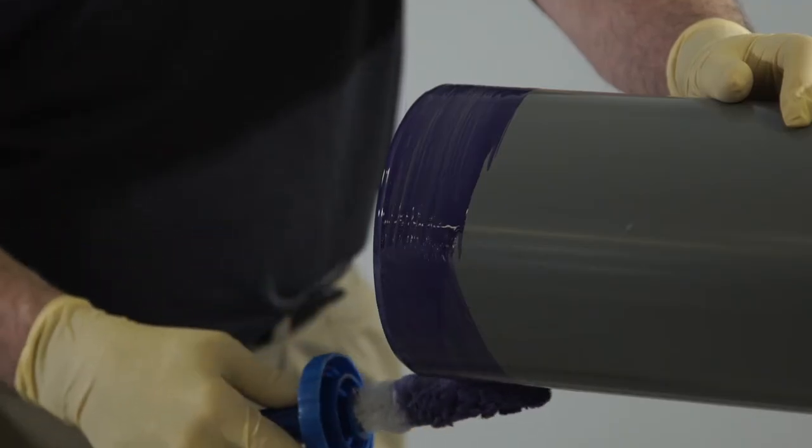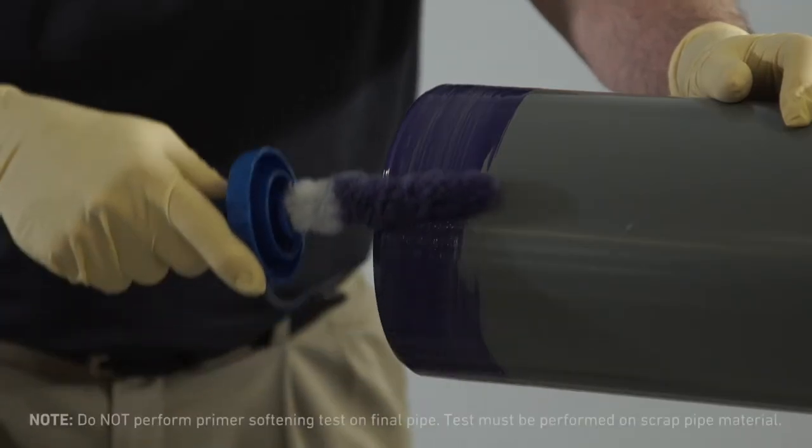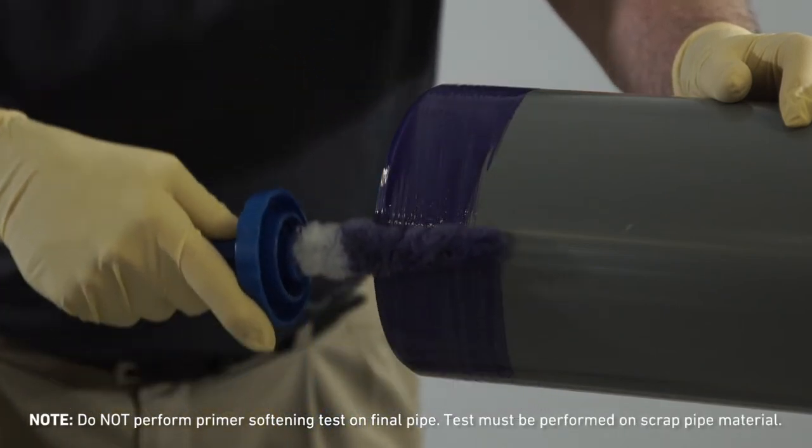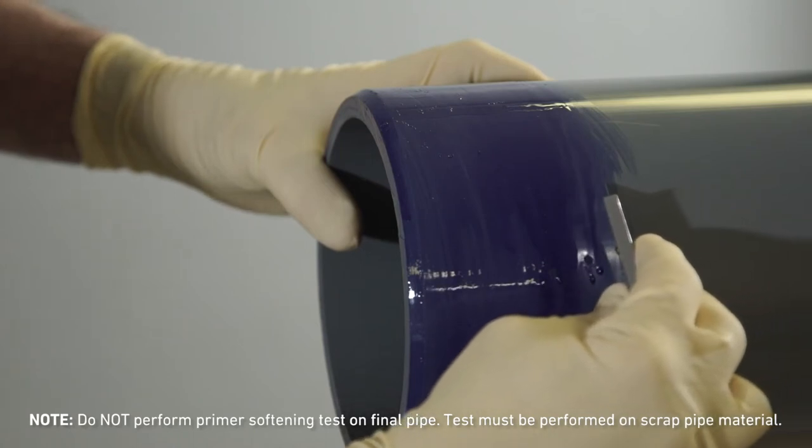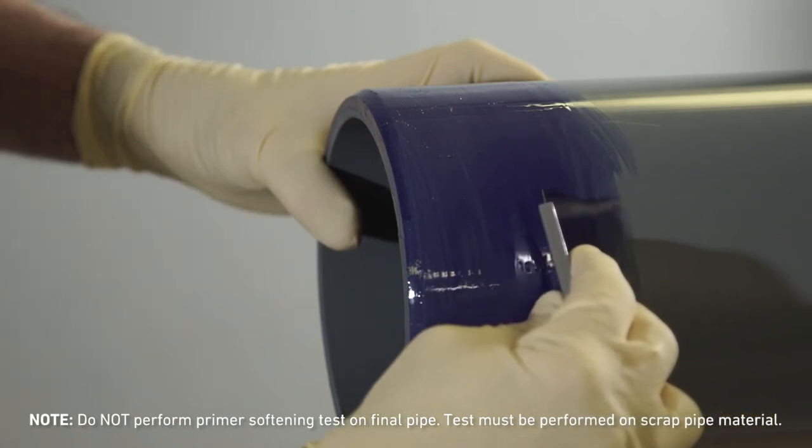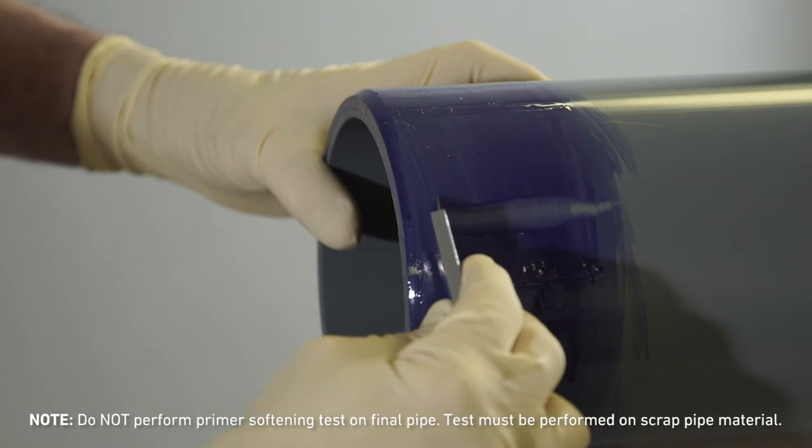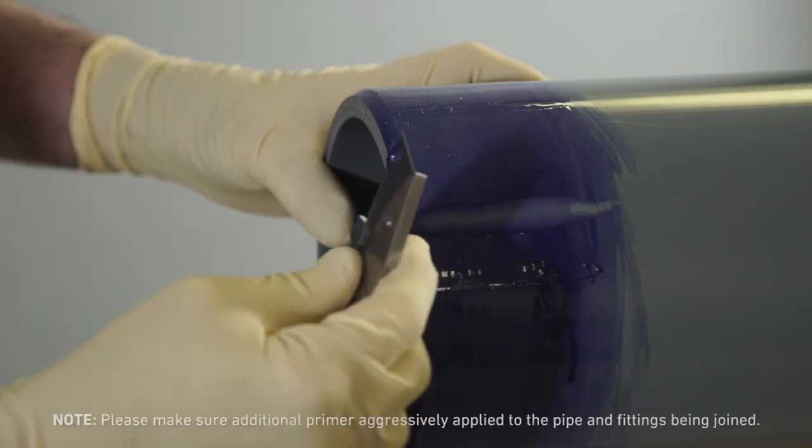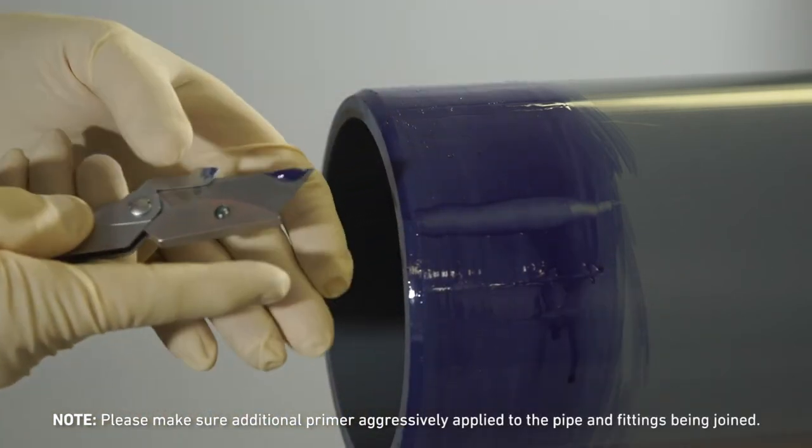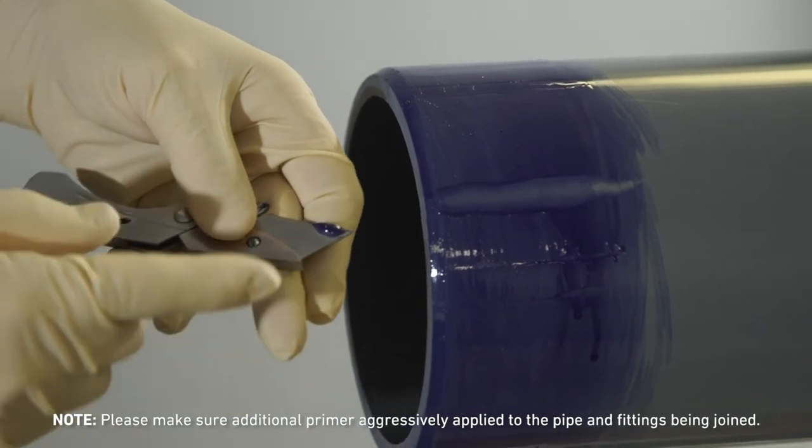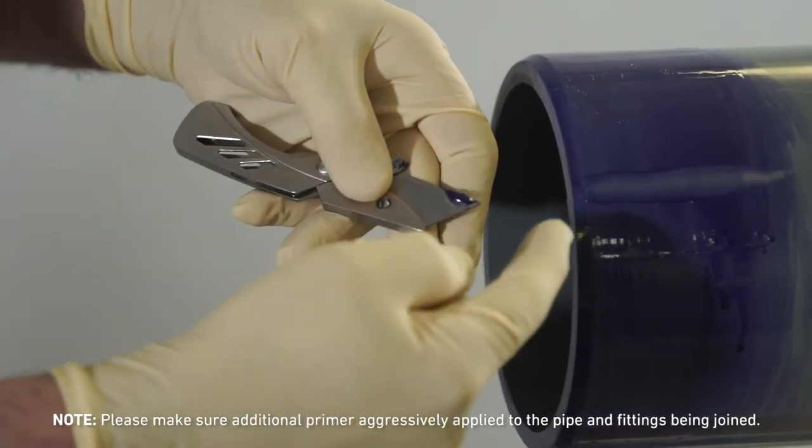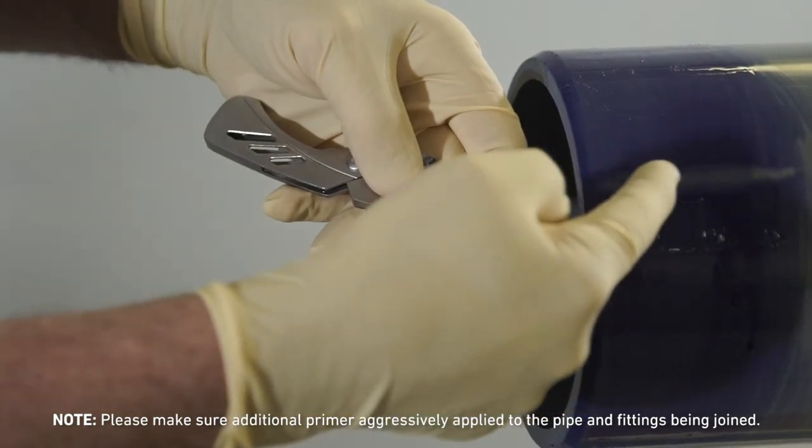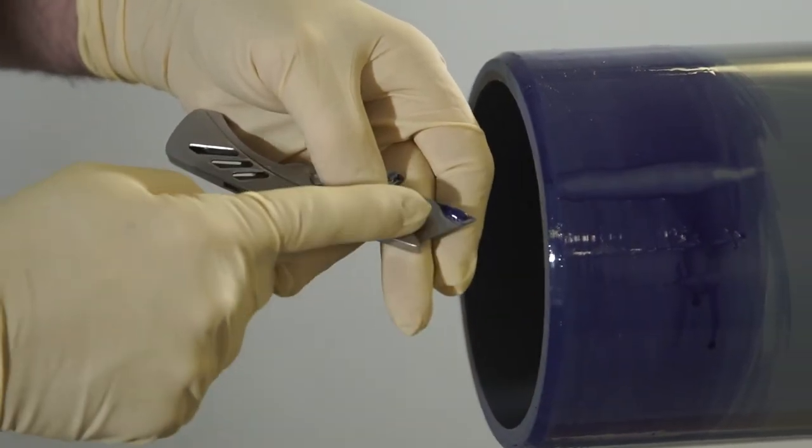Before solvent welding the assembly, ensure that the surface can be softened suitably by the primer on a piece of scrap pipe. This can be done using a pocket knife. The primer and pipe should scratch. This means that the wall is now sufficiently softened and ready for solvent cement. If the primer did not soften the OD of the pipe, please reapply additional primer. If successful, the following solvent welding process must be completed without interruption.